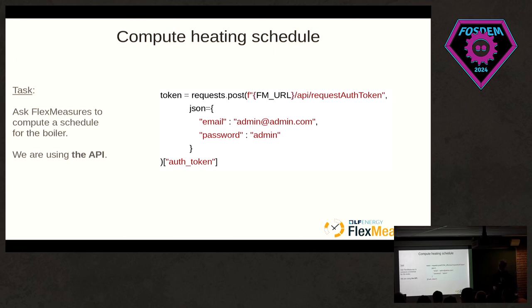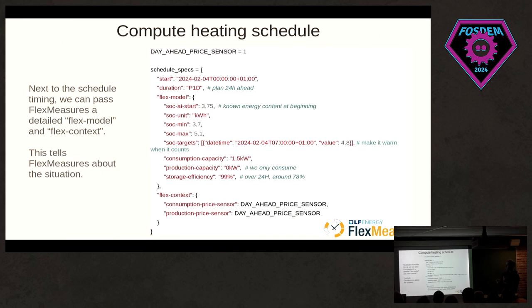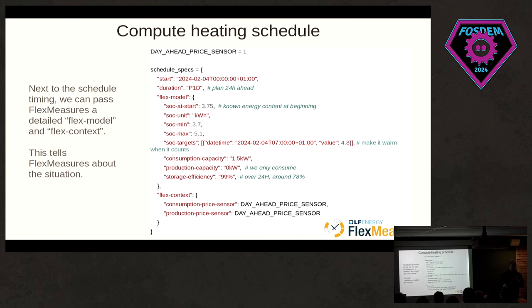The main part now: you want to actually tell FlexMeasures to give you an optimized schedule for your boiler. I'll show how to use the API directly. You have to have an authentication token. A lot of the time we spent making FlexMeasures was on how you configure the problem — how you tell FlexMeasures the constraints of the problem. In the back, FlexMeasures takes your information about your setup and your problem — basically you could call that business rules — and really translates that dynamically into a linear program.